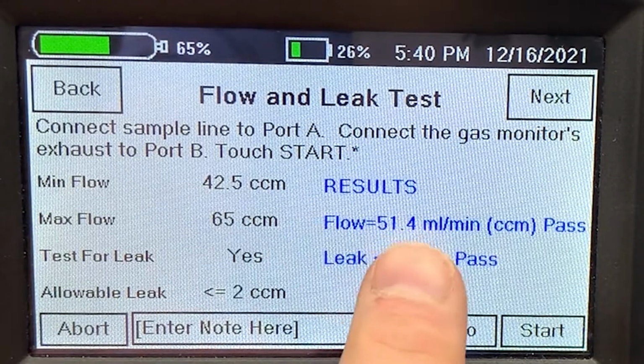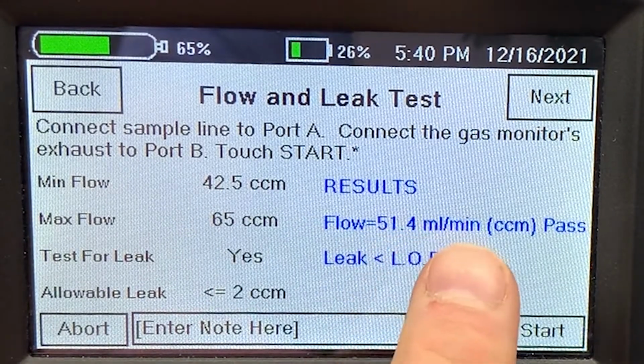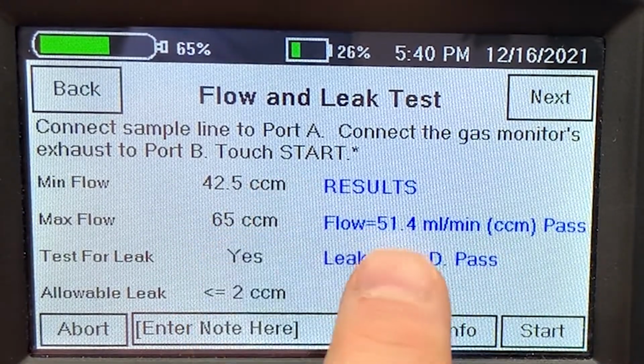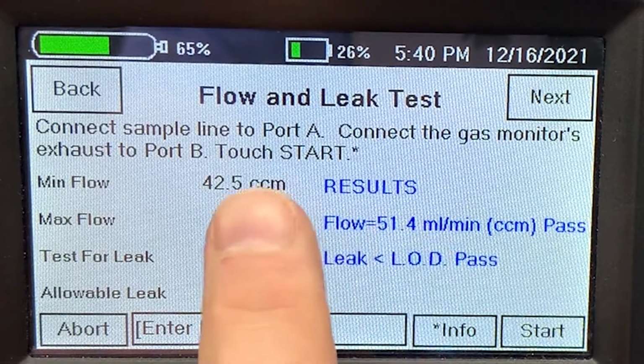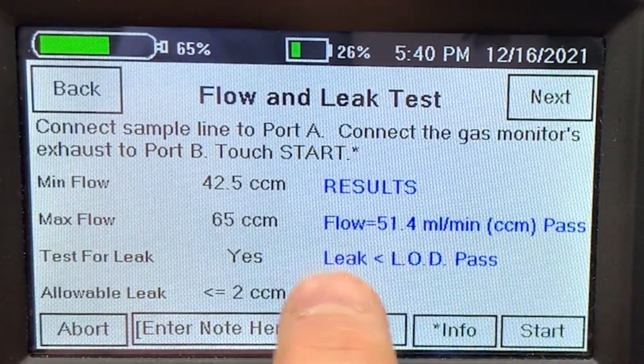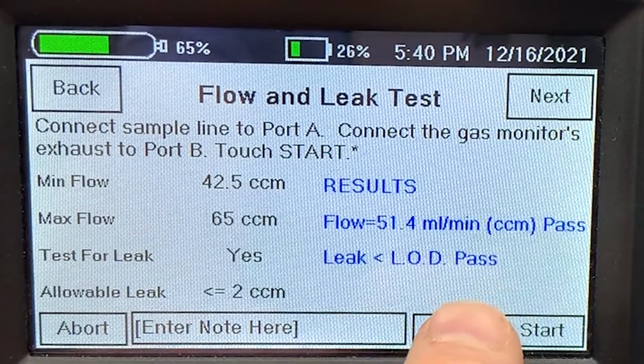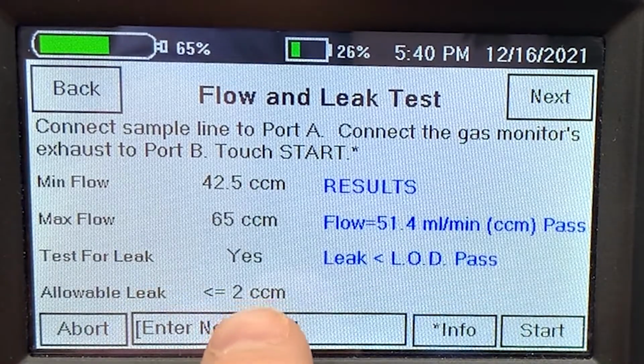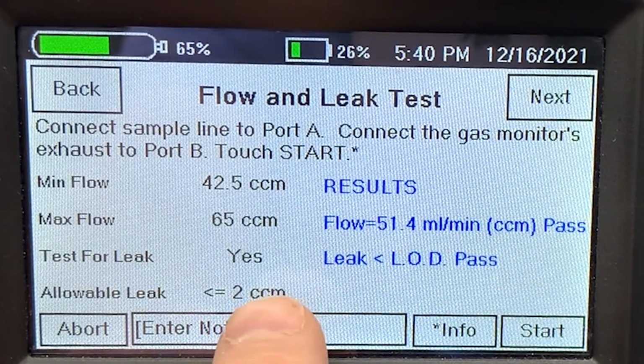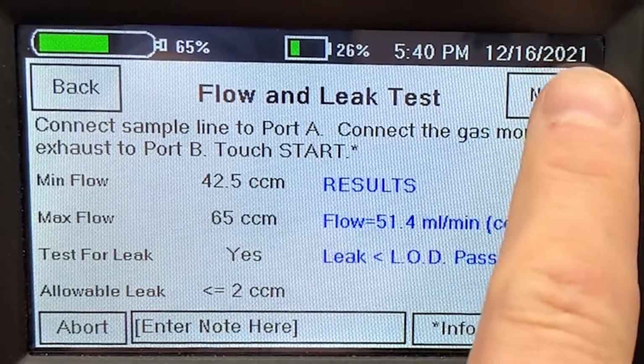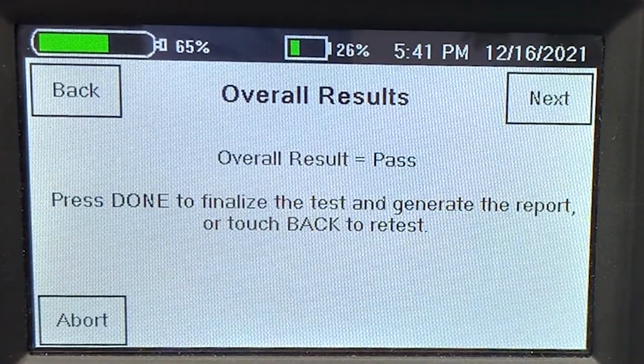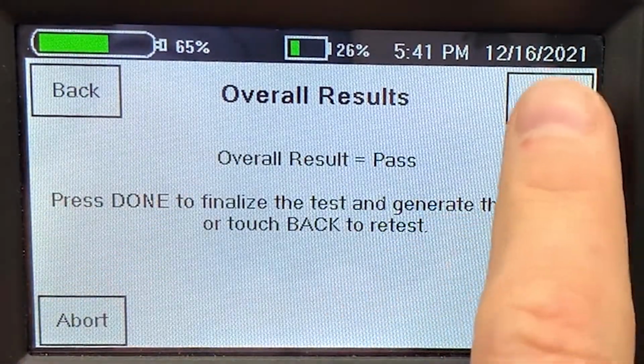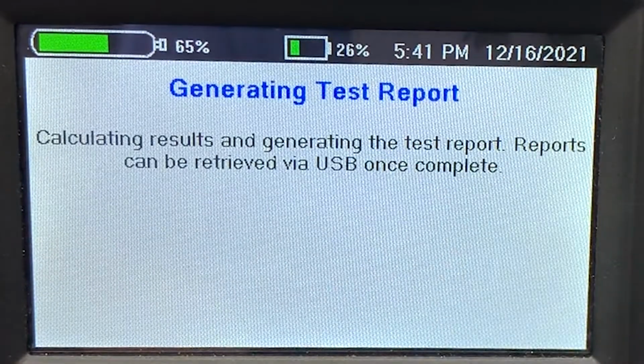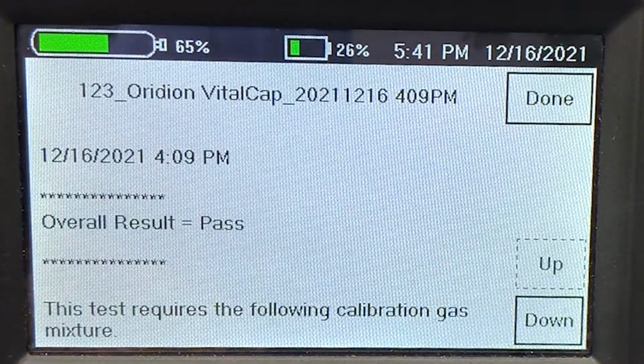So the flow rate was about 51 milliliters a minute, which is exactly what it should be. It should be about 50. It falls within the pass criteria. And the leak was less than the limit of detection, so it could have up to a 2 milliliter a minute leak. So that's a pass. So the overall result for the test is a pass. We hit next, we'll generate a test report, and we're done.